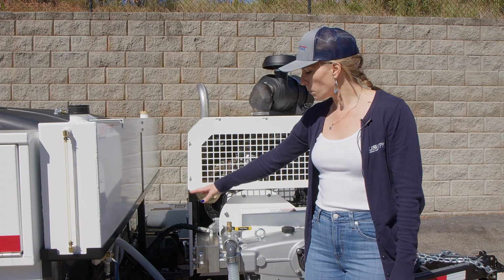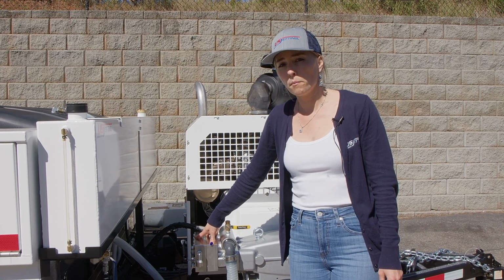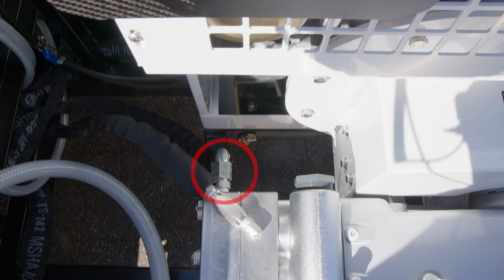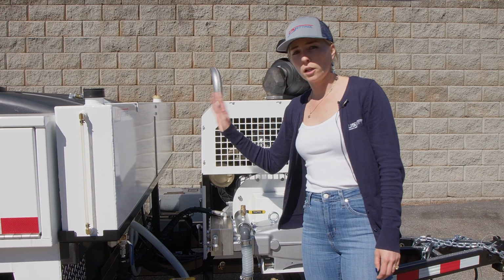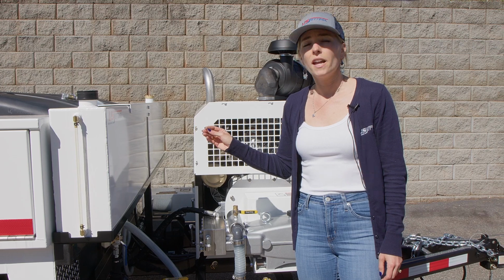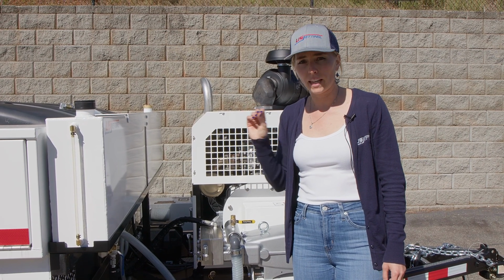Once you've eliminated the check valve, the next thing you want to inspect is whether there might be a problem inside the pump. You're going to remove the pump-to-reel hose, located on the inside of the pump, turn on the unit and the water, and see if the water is pulsating out of it.